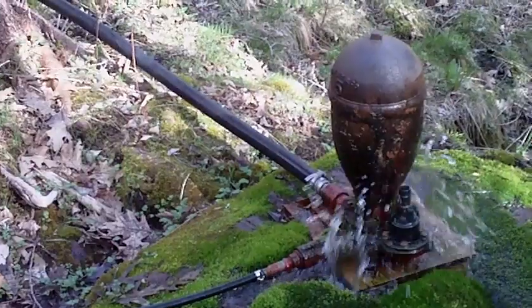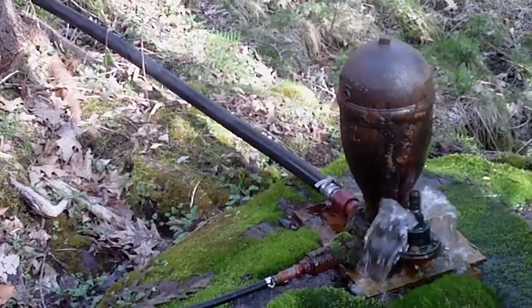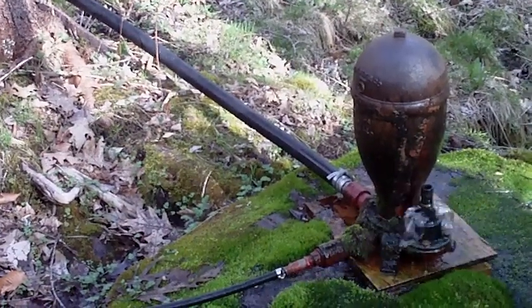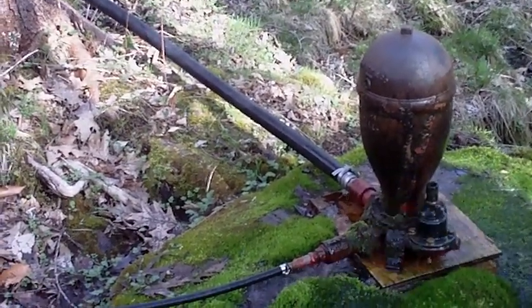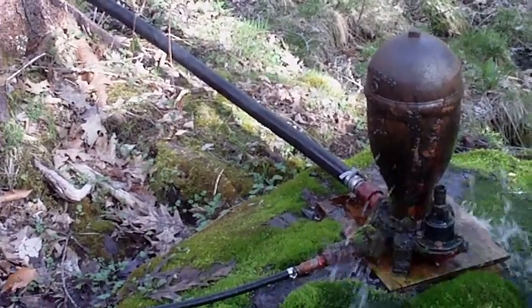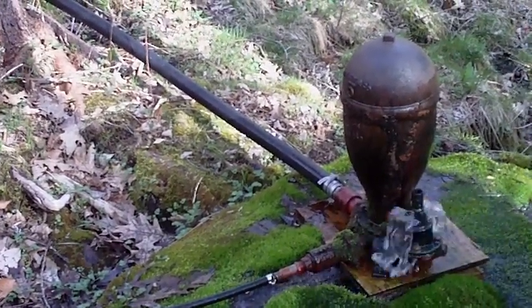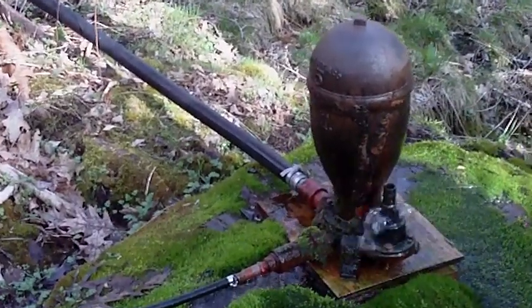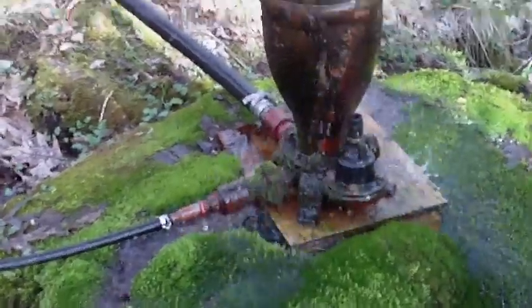Except coming down here sometimes — that light bulb thing will fill up with water because it should actually be full of air. It's like putting carbon into pop; eventually the air gets pushed right into the water, which kind of aerates it. But its main function is: after the water hits that check valve, it's like shutting your taps off really hard at home — it creates that jolt that sends water up the smaller pipe, and that bulb cushions the backflow so you get a more even flow.